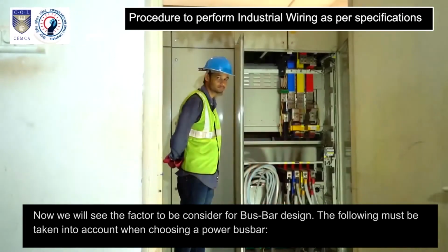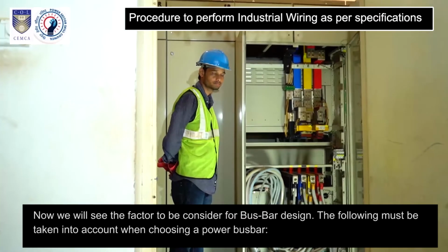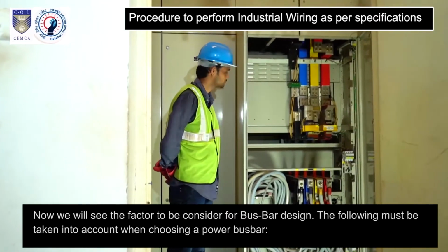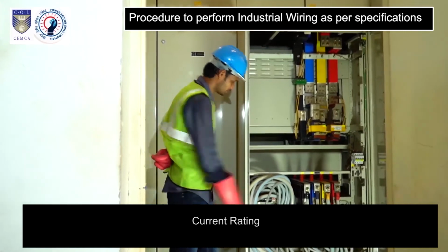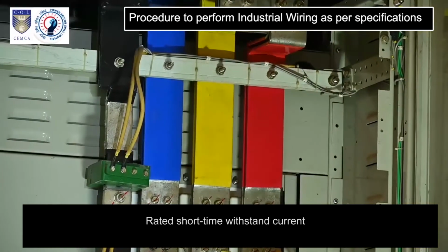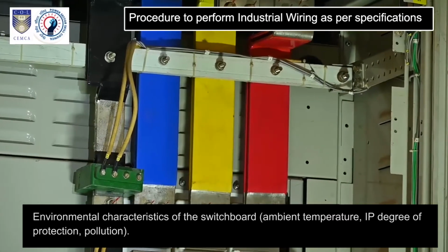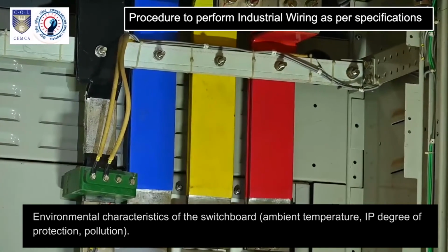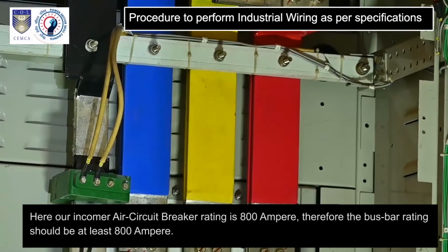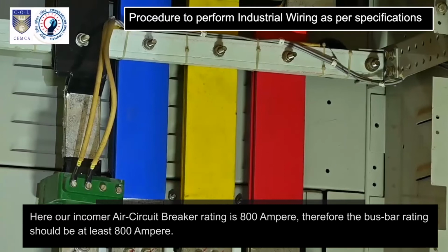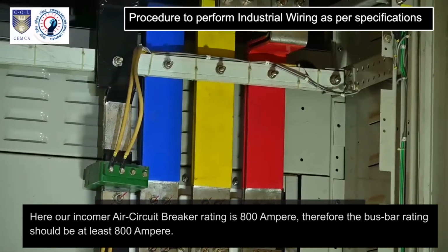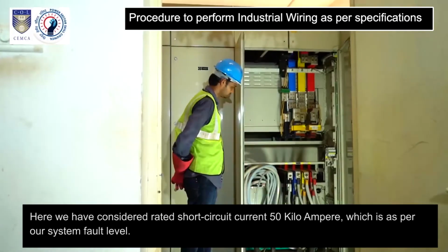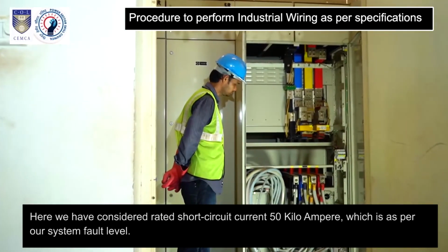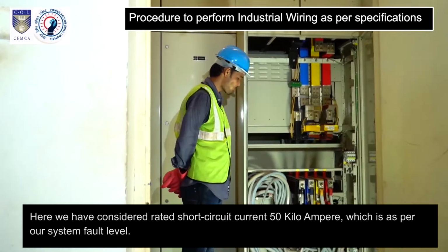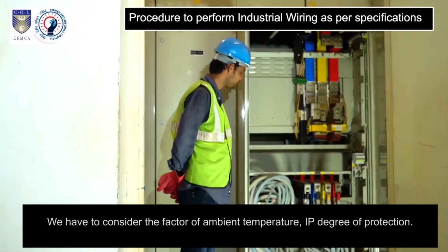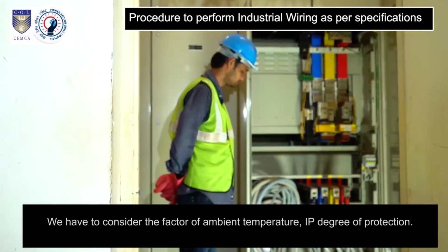Now we will see the factors to be considered for busbar design. The following must be taken into account when choosing a power busbar: current rating, conditional short circuit current, rated short time withstand current, environmental characteristics of the switchboard, ambient temperature, IP degree of protection, pollution. Here our incomer air circuit breaker rating is 800 ampere. Therefore the busbar rating should be at least 800 ampere. Here we have considered rated short circuit current 50 kiloampere, which is as per our system fault level. We have to consider the factor of ambient temperature, IP degree of protection.